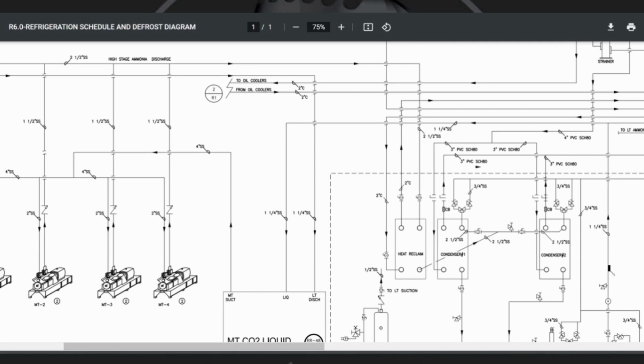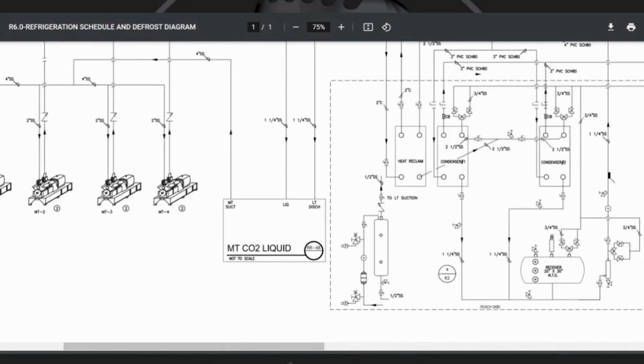Okay. Then the vapor, we don't generally do any condensing in that heat reclaim heat exchanger. It's really a desuperheater. Okay. The gas comes out of there, it goes into a T and goes to two plate heat exchangers that are actually the condensers. Condenser 1 and condenser 2. Yep. Condenser 1, condenser 2. And they just run in parallel. The warm vapor is then condensed into a liquid, and it tees into a liquid line.